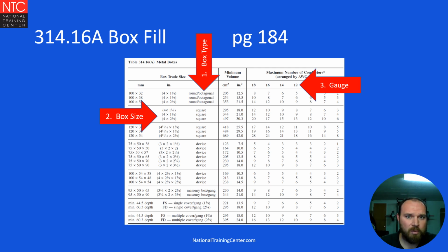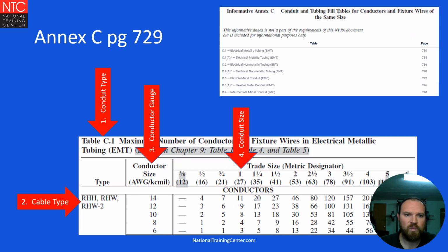Here's how we recommend utilizing the box fill table. Identify the type of box you're being asked about first. Then move over to the left, identify the size of that box, put your finger down, scroll over, and find the gauge of cable that you need to know about. That's how we recommend using the box fill table.